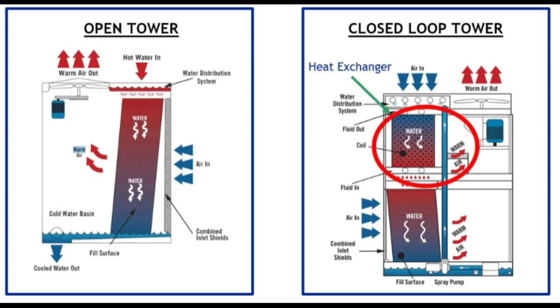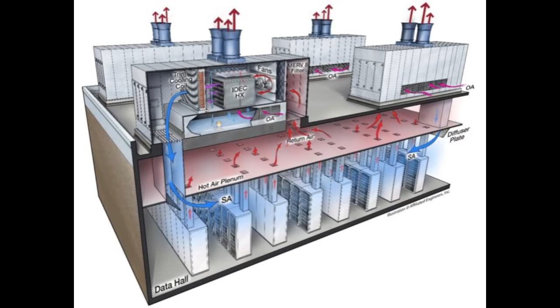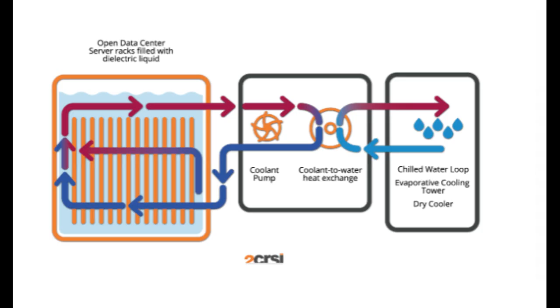Another method would be immersion cooling, where servers and IT components are submerged in a non-conductive liquid to manage heat. This process allows higher-level computers to work faster and is efficient not only in power but also in water usage, since no evaporative cooling is needed, leading to less pollution.